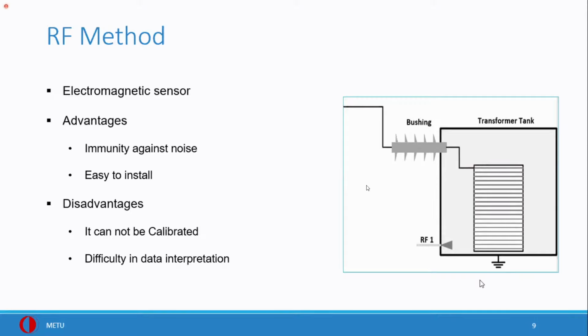The main advantage of this method is that we can measure at much higher frequency, far above the 50 hertz of our power system. Some disturbances go up to 10 or 20 megahertz, but above that we usually don't have any source of disturbance.